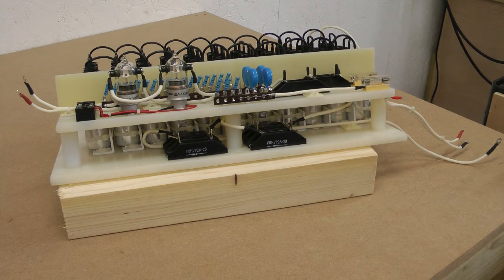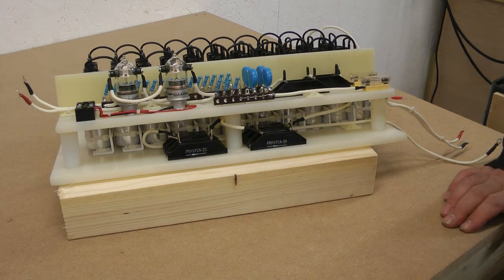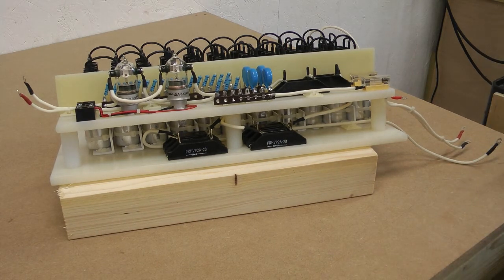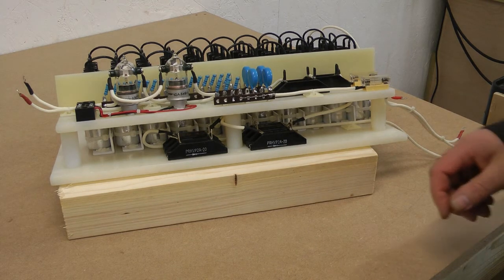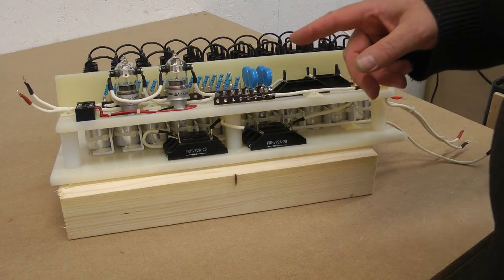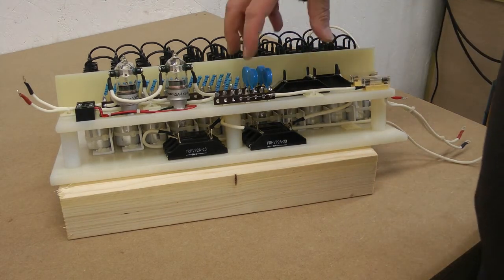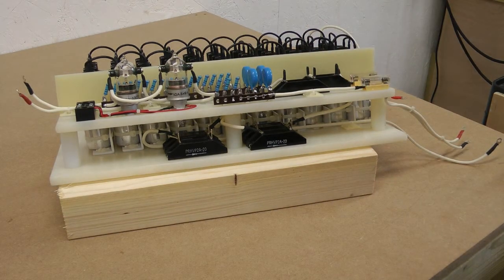Now, of course, the front panel is good because you have a plastic shafted rotary switch on the front, and that is only switching the 24 volts to one relay or the other. So you don't get any of the high tension from this end anywhere near the front panel, which is good for safety when you're working with various experiments.